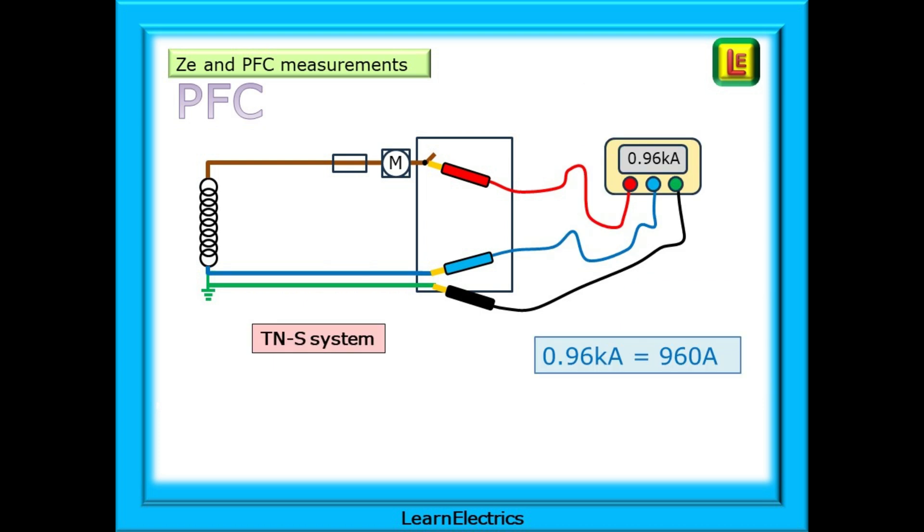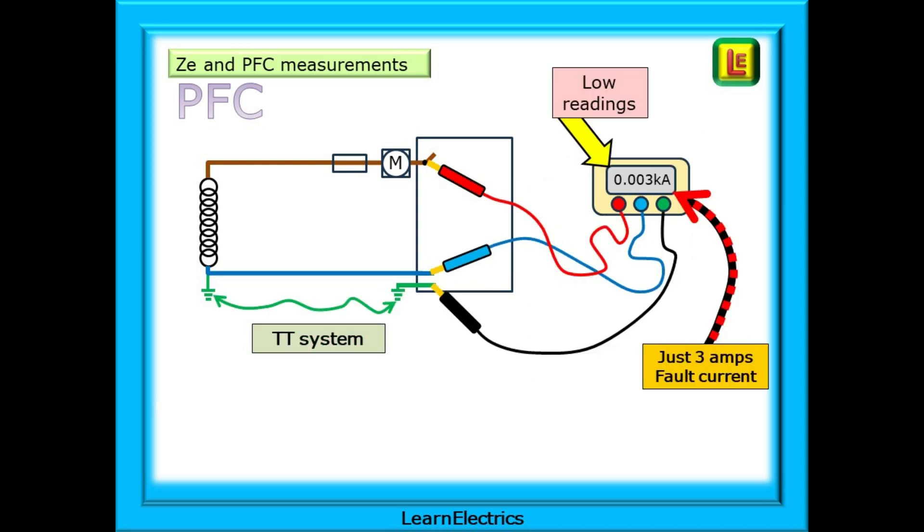The same PFC test method is applied for TNS systems, two wire or three wire. Shown here the meter is displaying 0.96 kiloamps or 960 amps. Get used to working with zeros and decimal points in the test results. And now for a TT system.